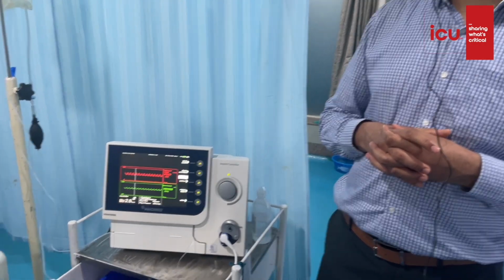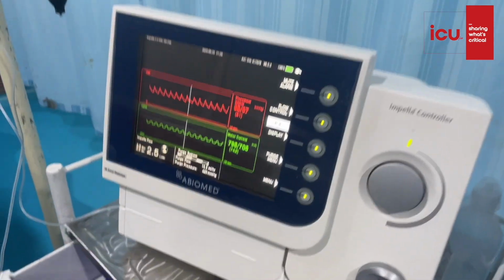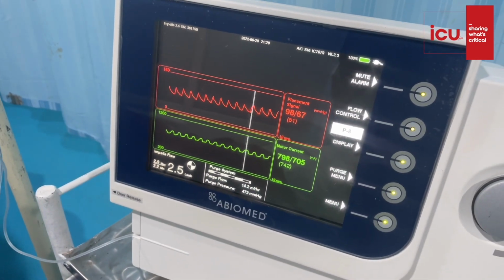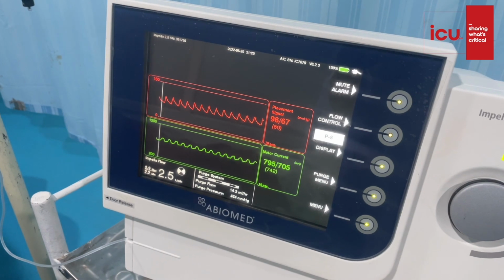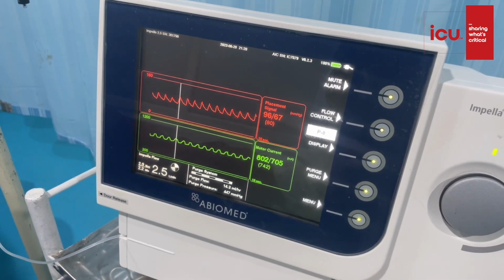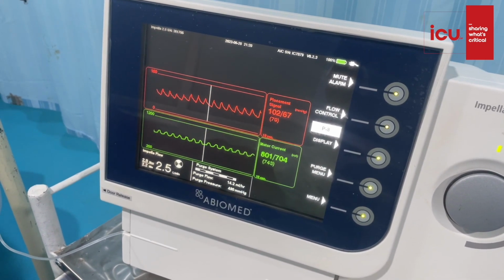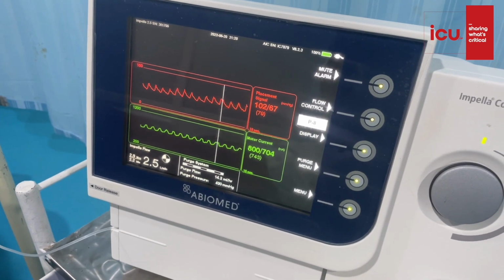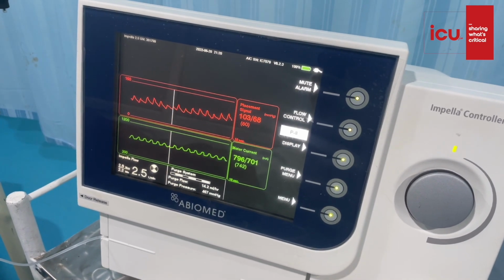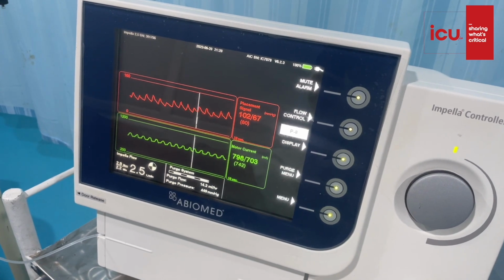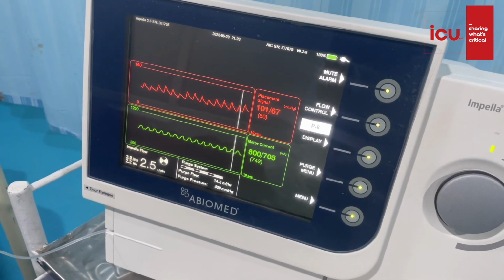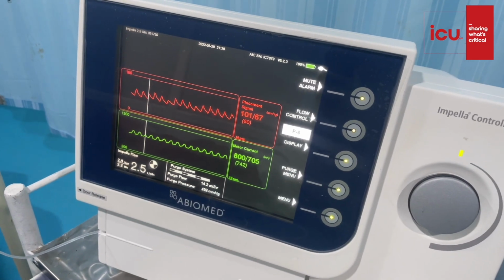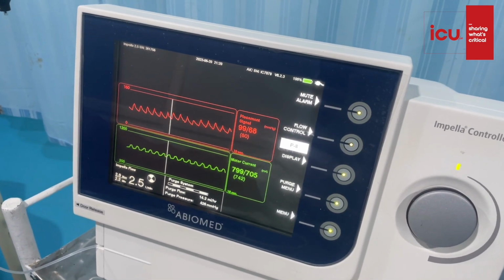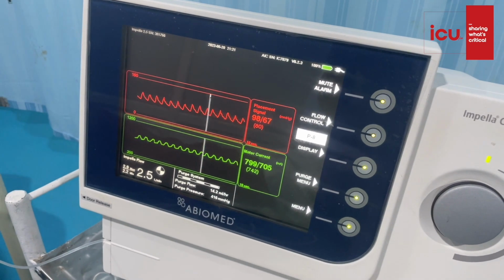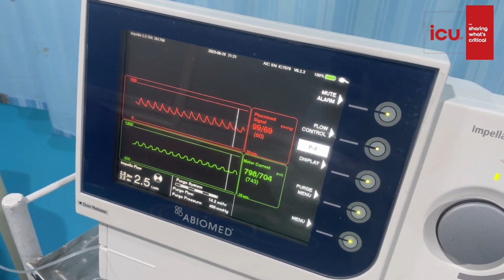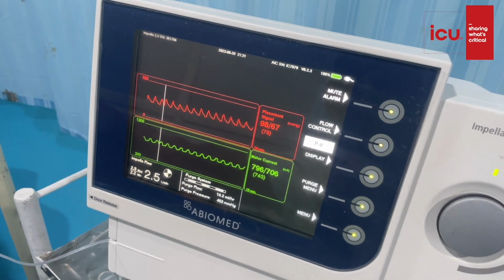So what I can understand from this is these two graphs help you determine the position of the Impella, whether it is in the aorta or in the ventricle. If they are both in the ventricle, then your motor current signal will become flat. If it is flat, then it means it is not in the two separate chambers. But the pulsatile one, the BP which is recorded by the placement signal, if it is flat, then it can be due to low cardiac activity, a low cardiac output state. Yes. And we rely more on the mean arterial pressure rather than the systolic and diastolic pressure when it comes to Impella. Correct.